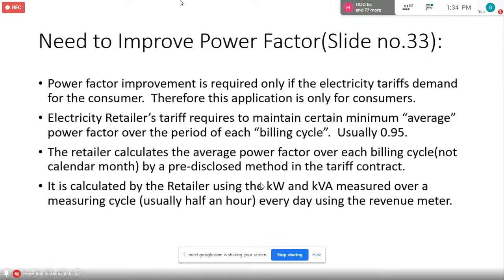All right, so that was the basics of capacitance. Now we talk about power factor improvement. Why do we need to improve the power factor? Power factor improvement is required only if the electricity tariff demands it from the consumer. Therefore, this application is only for consumers. Power utilities don't need to improve their power factor. It's the consumer who has to improve the power factor so that automatically the power utility's power factor is improved. So the onus is on the consumer, not the power company. And if the consumer doesn't, then the power company will penalize it.